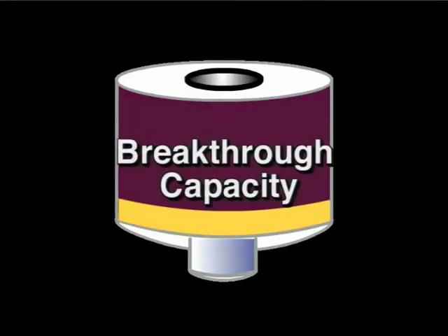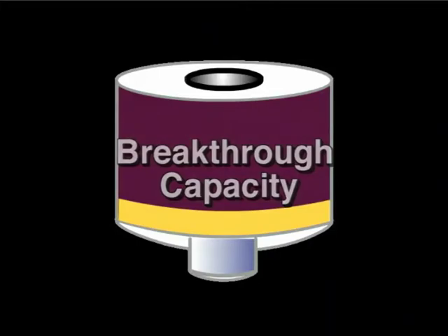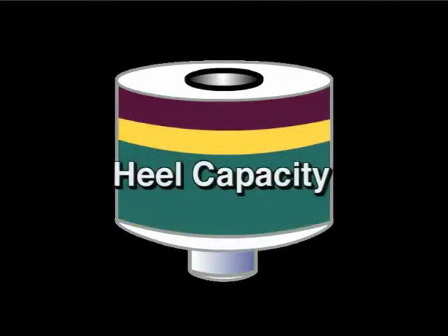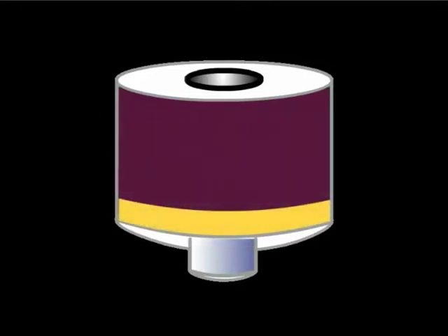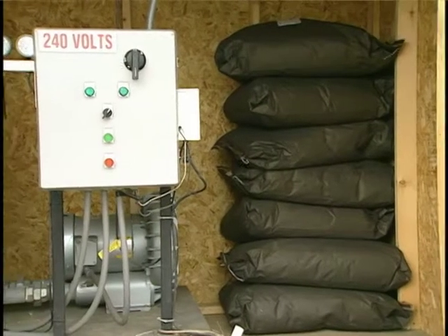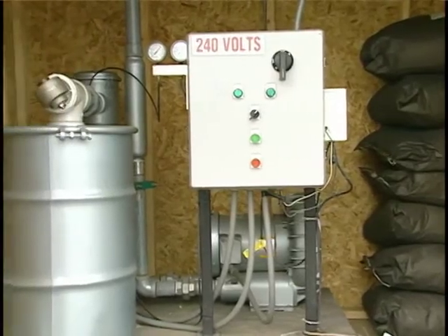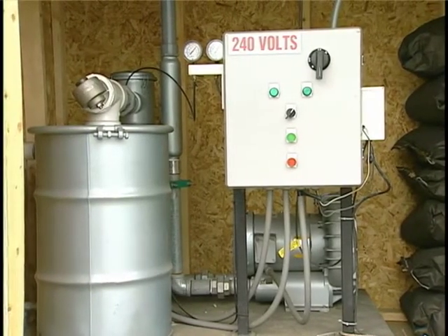Saturation capacity is the maximum amount of organic material the carbon can hold. Breakthrough capacity is the amount of organic material the carbon can hold before significant organic concentration begins to exit or break through the carbon bed. Heel capacity is the amount of organic material remaining in the carbon bed after it has been regenerated. Working capacity is the difference between breakthrough capacity and heel capacity, and represents the amount of organic material that can be absorbed in each operating cycle. A typical working capacity is 10 to 20 pounds of contaminant per 100 pounds of carbon.